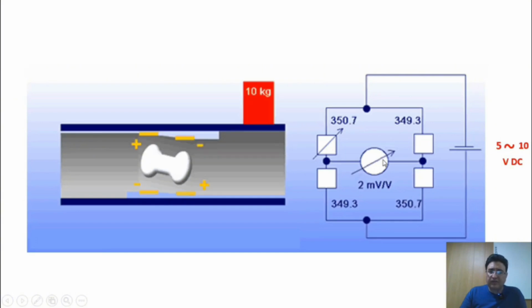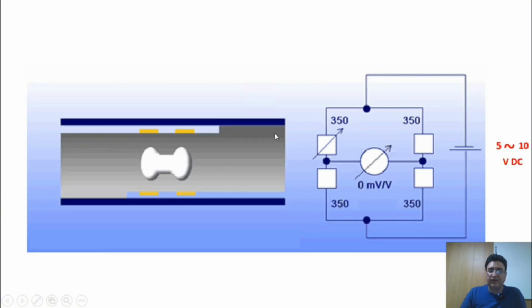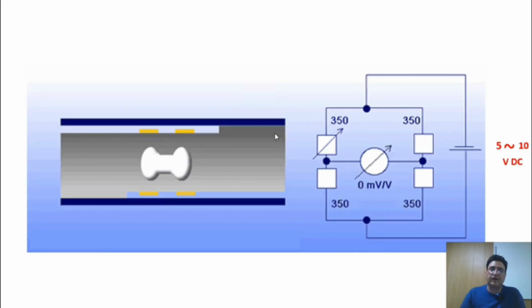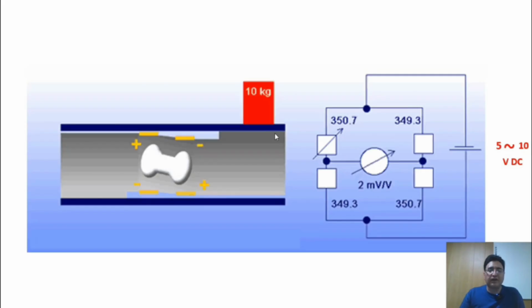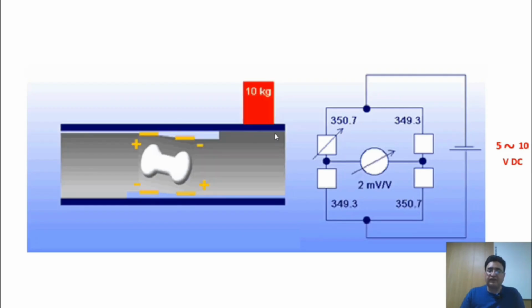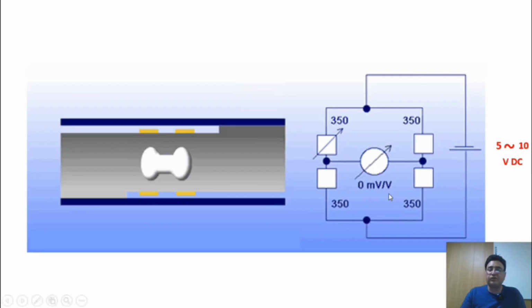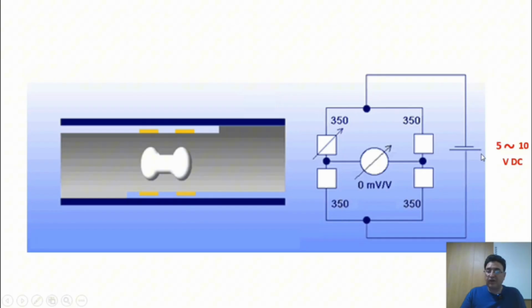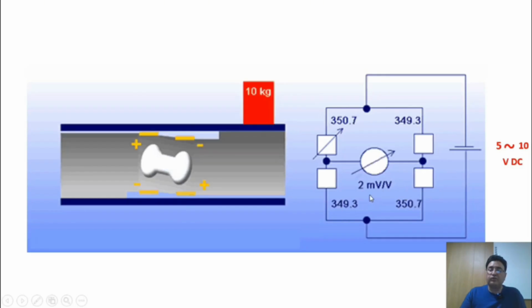The output of this load cell is a signal in millivolts. If you look at the load cell's parameters, there's a parameter called rated output, which actually shows us the rate of change of the load cell's output in millivolts. In SEWHA load cells, this rated output is 2 millivolts per volt. That means if our initial input voltage is just 1 volt, our corresponding output will be 2 millivolts.